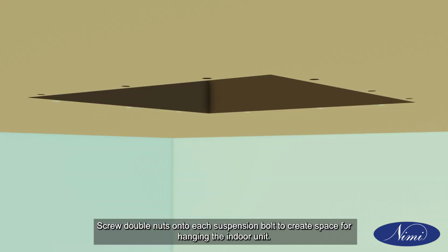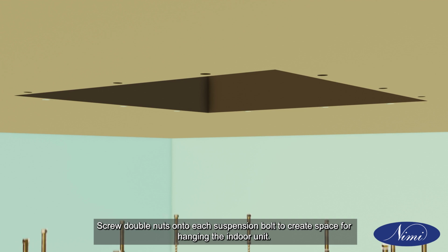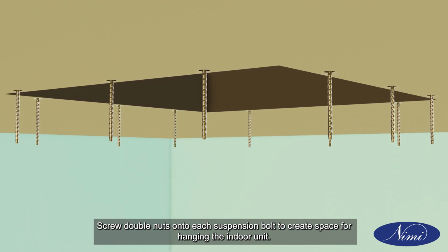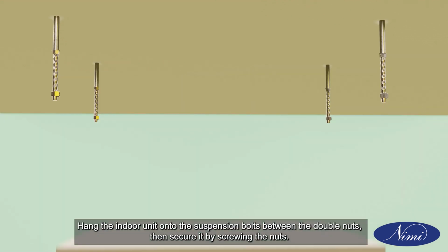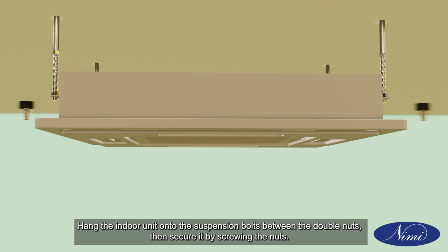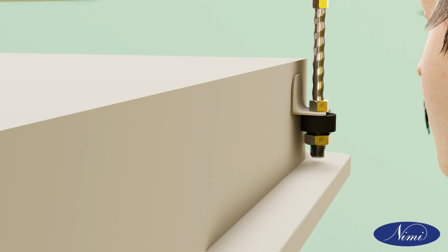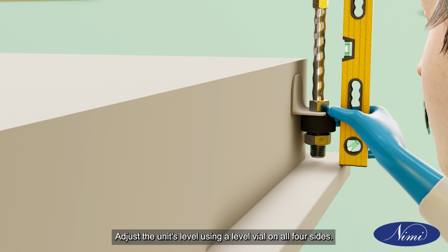Screw double nuts onto each suspension bolt to create space for hanging the indoor unit. Hang the indoor unit onto the suspension bolts between the double nuts, then secure it by screwing the nuts. Adjust the unit's level using a level vial on all four sides.